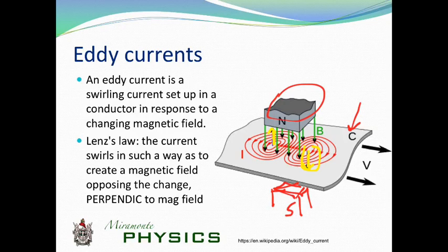So one way, from an engineering perspective, to prevent that from happening is to put little slices in the metal, little gaps, that will prevent those little currents from running around in circles. That's why we had the little strips in there. Sometimes in metals we actually laminate them. So we'll have a sheet of metal, and then an insulating glue, and then another sheet of metal.